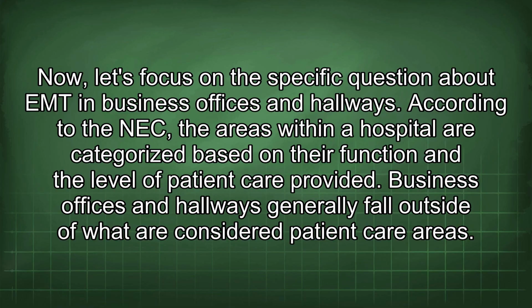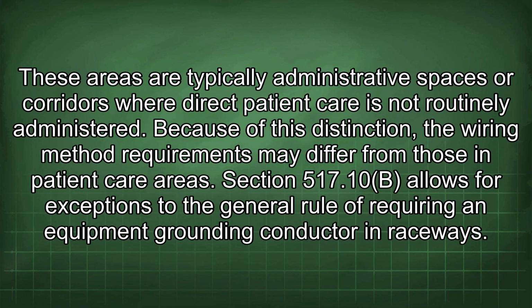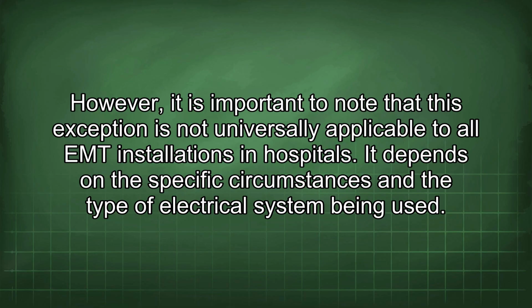According to the NEC, the areas within a hospital are categorized based on their function and the level of patient care provided. Business offices and hallways generally fall outside of what are considered patient care areas. These areas are typically administrative spaces or corridors where direct patient care is not routinely administered. Because of this distinction, the wiring method requirements may differ from those in patient care areas. Section 517.10(B) allows for exceptions to the general rule of requiring an equipment grounding conductor in raceways. However, it is important to note that this exception is not universally applicable to all EMT installations in hospitals. It depends on the specific circumstances and the type of electrical system being used.